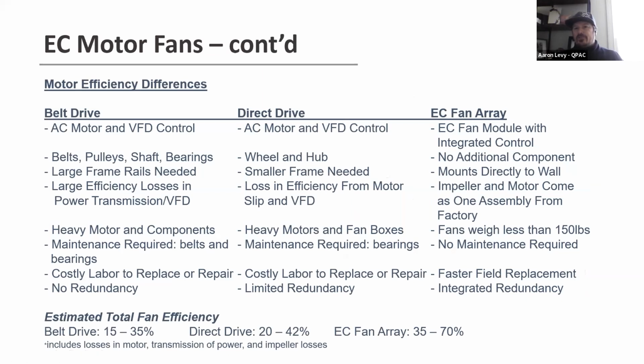A lot of the differences from what may currently be in there with either a belt drive or direct drive system versus an EC fan array is that the EC fans all have their integrated controls. They're very similar to a VFD in the fact that it controls the speed. It just goes about it a different way. So instead of controlling the Hertz profile and changing that speed through the sine wave, we change it just from how we control the flow of voltage going into the fan itself. The Hertz profile always stays at 60. The voltage always stays at mainline voltage, be it 460, 230, 208, 3-phase. And it just controls the pulse of that voltage going to the stator itself.